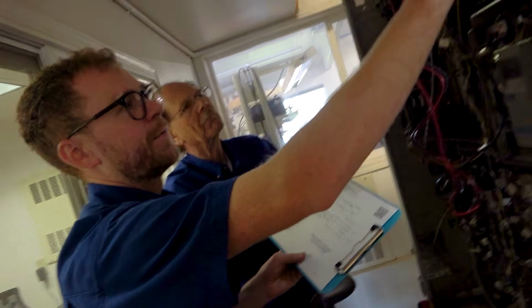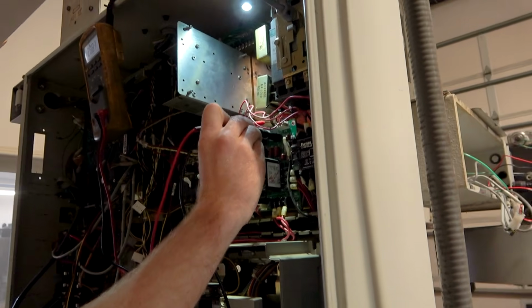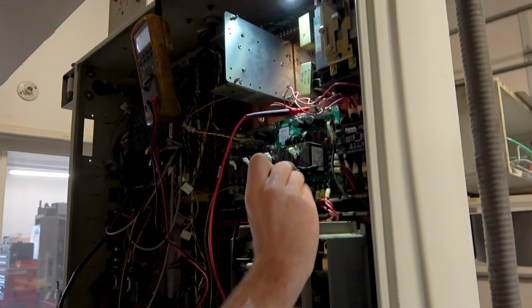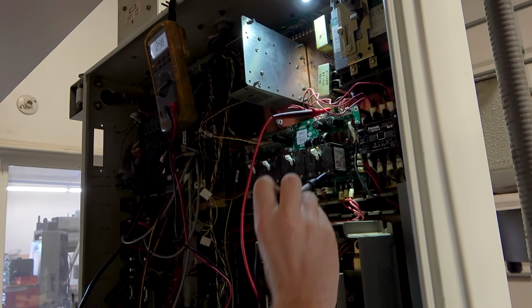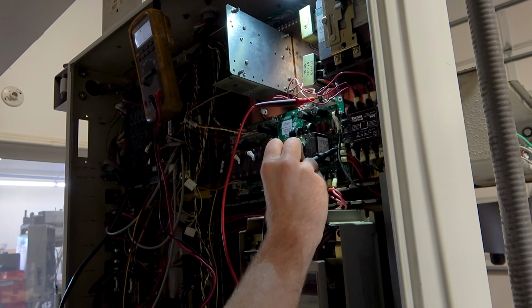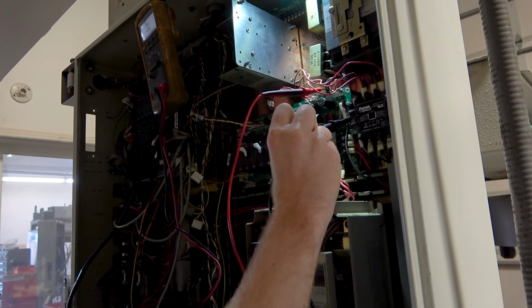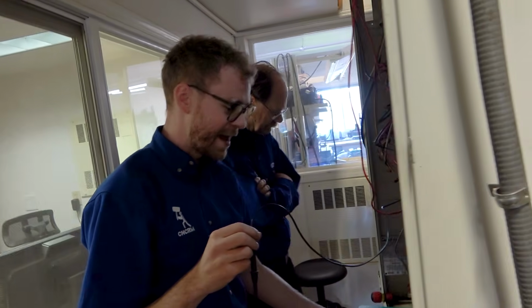Let's check here - I've got 28 volts there. Now, if this normally open contact is functioning correctly, I shouldn't see any voltage here. And if I push this in, I should see voltage there, and it should latch and boot up.